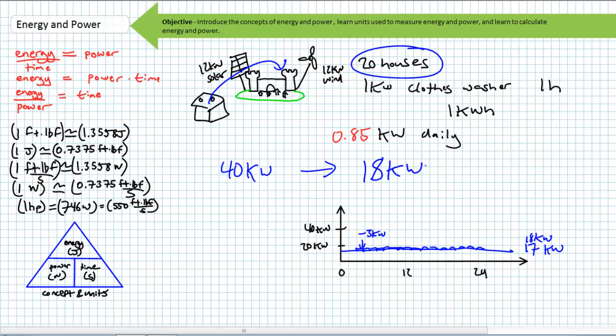Consider our centralized 40 kilowatt genset as the worst case scenario, the dumbest and most inefficient approach, compared to a smart grid with efficiency upgrades. If each house consumes 850 watts constantly, you've got a base load of 17 kilowatts. Add a properly time-managed 1 kilowatt peak distributed 20 times over 24 hours, and the generator could be downsized to 18 kilowatts. The negawatts generated by simple rethinking of how you generate, manage, distribute, and use energy is 22 kilowatts — power you don't have to generate just by being smart.